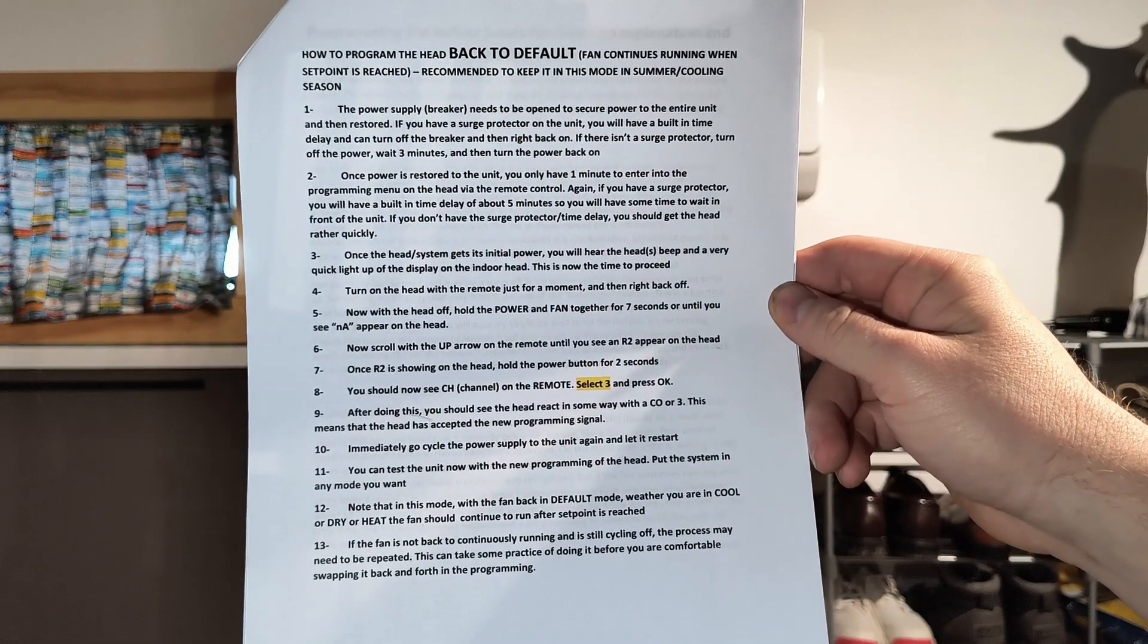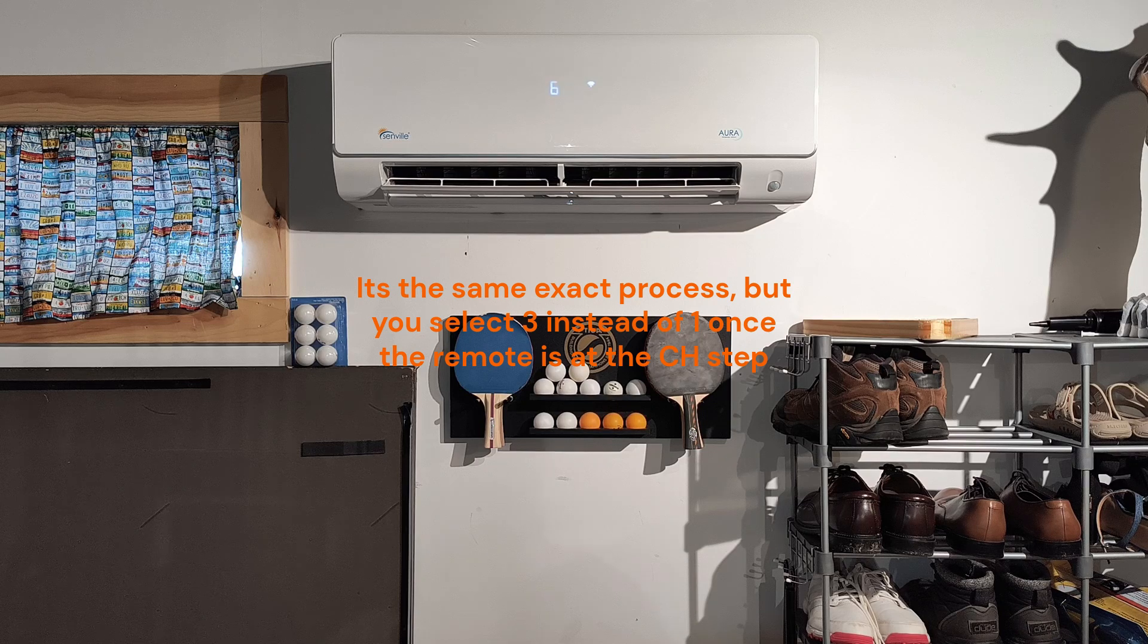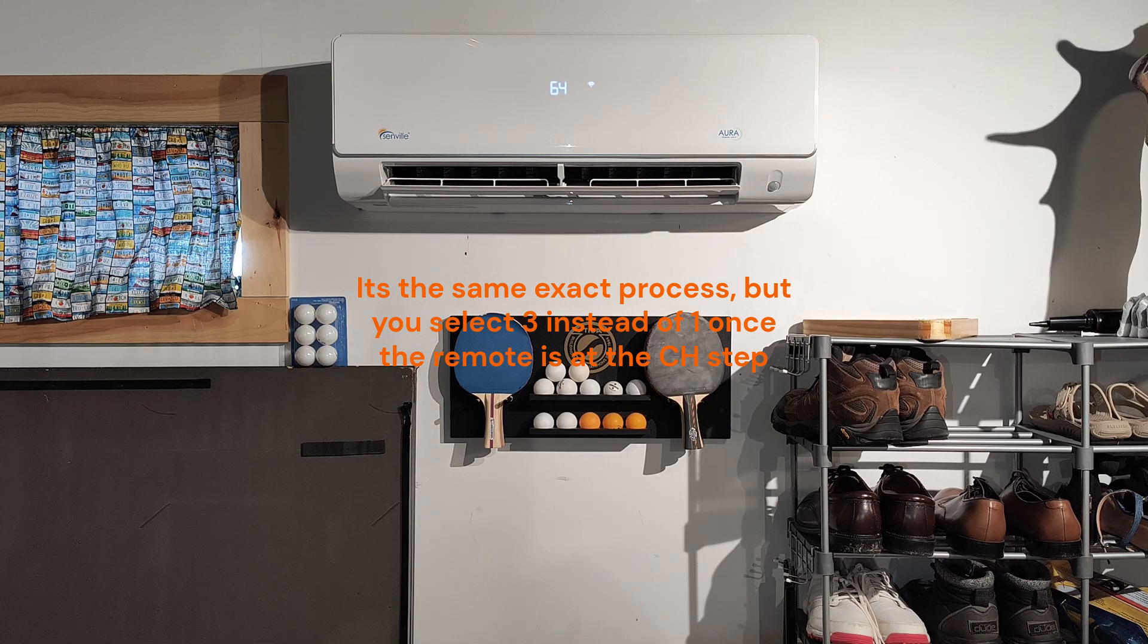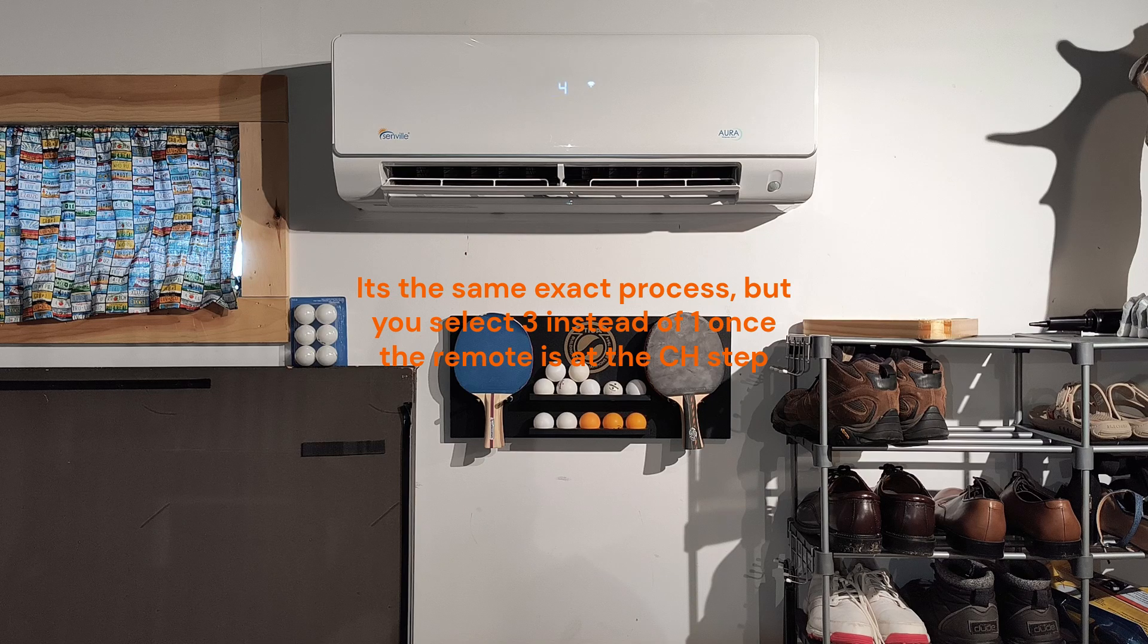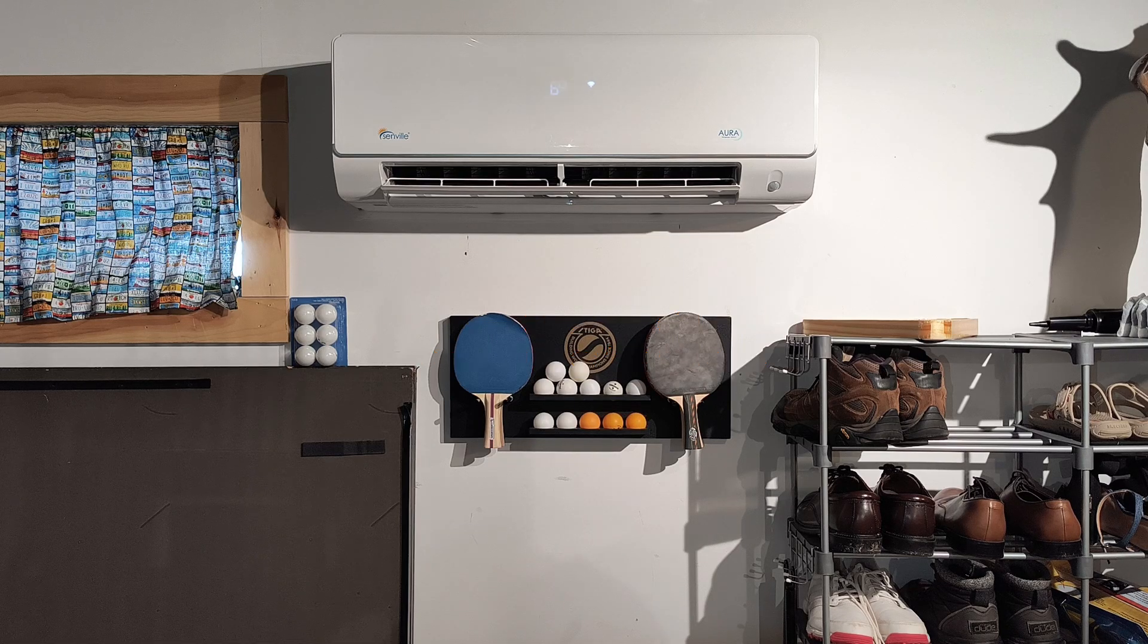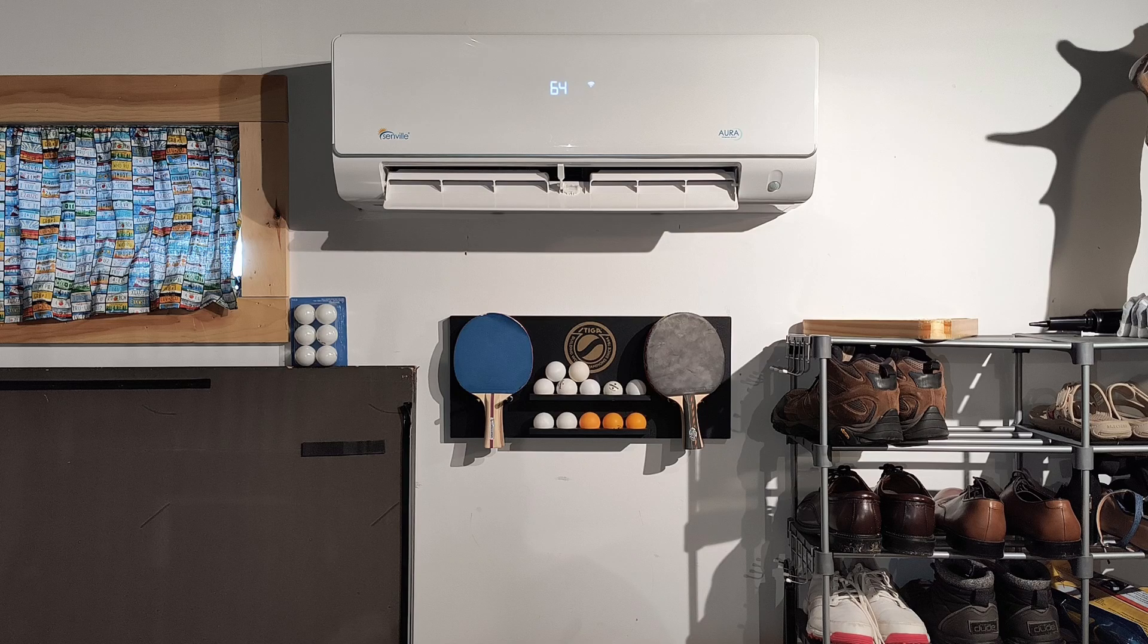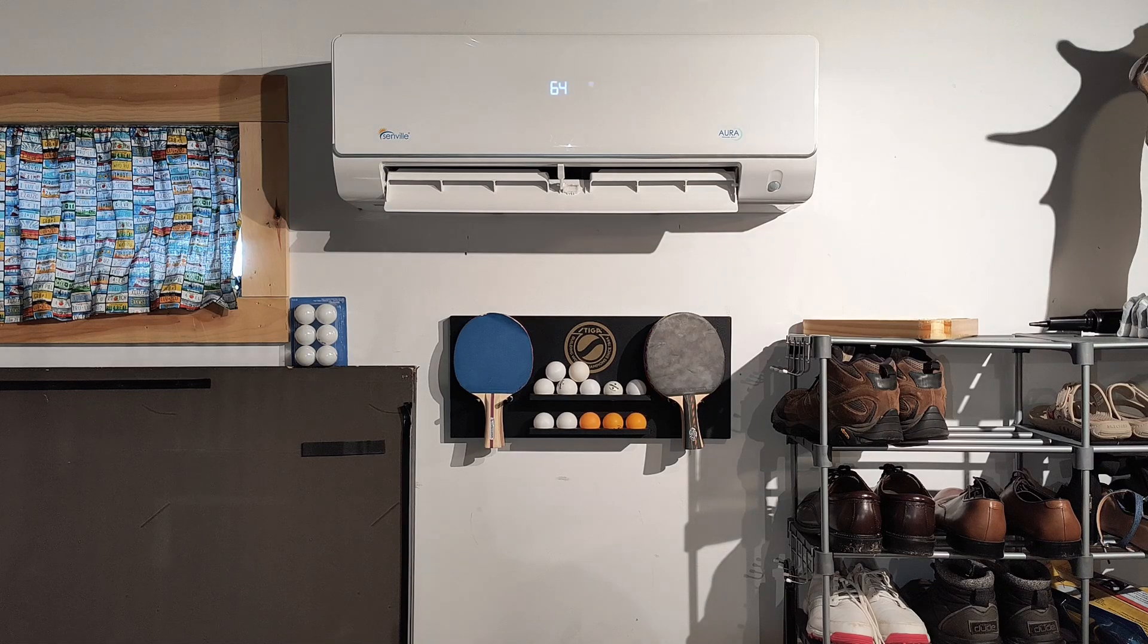And if you cared, you'd put that back into that mode for summer when you get it in AC mode, because it is better to have the fan continuously running, especially in cooling mode. Because when it cycles on and off a lot, it's not great for the fan in terms of it getting kind of skanky with mildew and stinky smells. It's better to leave that fan running continuously because the fan wheel is able to dry out better. So this is really only recommended in heat mode when you're having problems with an overshooting temperature, typically in a small bedroom.